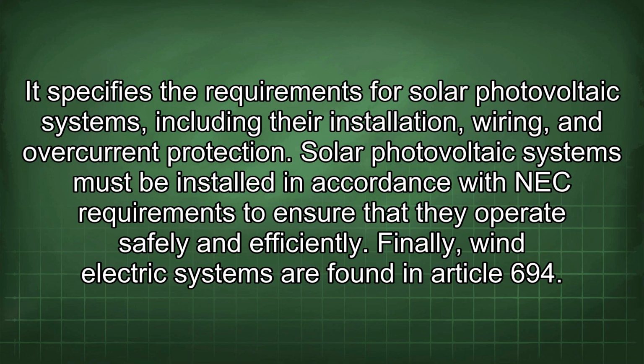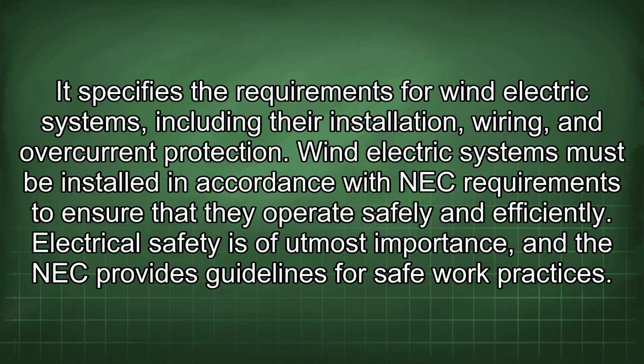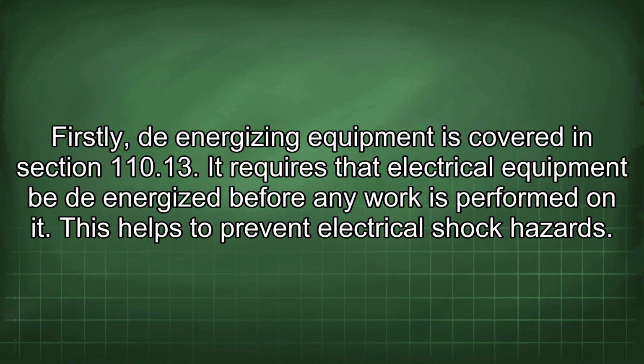Finally, wind electric systems are found in Article 694. It specifies the requirements for wind electric systems, including their installation, wiring, and overcurrent protection. Wind electric systems must be installed in accordance with NEC requirements to ensure that they operate safely and efficiently. Electrical safety is of utmost importance, and the NEC provides guidelines for safe work practices. Firstly, de-energizing equipment is covered in Section 110.13. It requires that electrical equipment be de-energized before any work is performed on it. This helps to prevent electrical shock hazards.